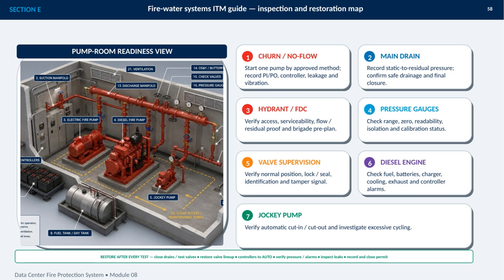For the diesel engine, check fuel, batteries, charger, cooling, exhaust, and controller alarms. Finally, confirm the jockey pump cuts in and out automatically, and investigate excessive cycling. After every test, restore the system deliberately. Close drains and test valves, return the valve lineup, place controllers in auto, verify pressure and alarms, inspect for leaks, and record and close the permit.